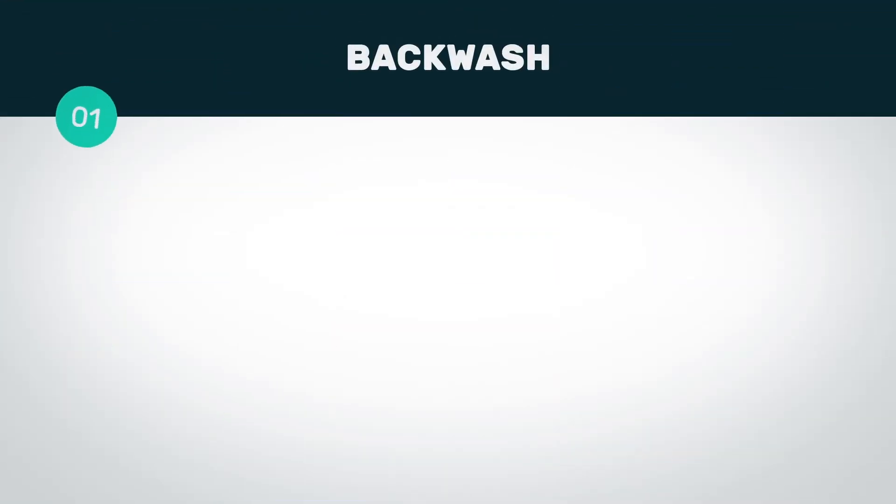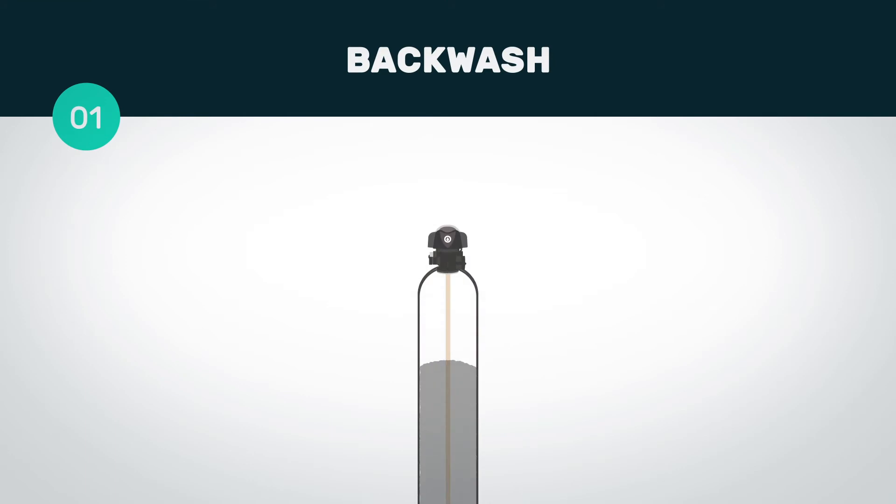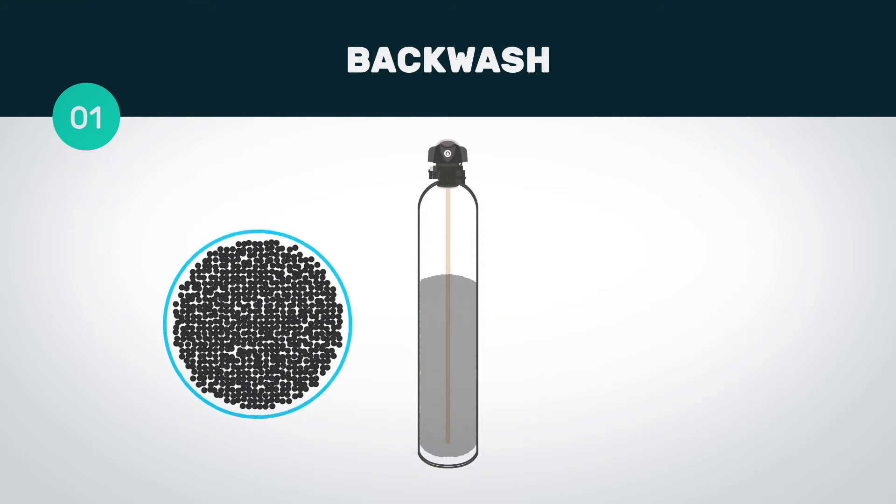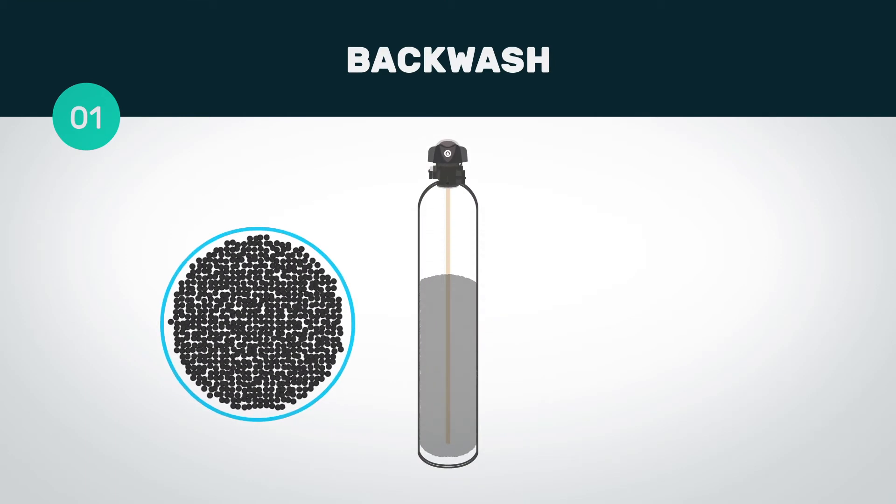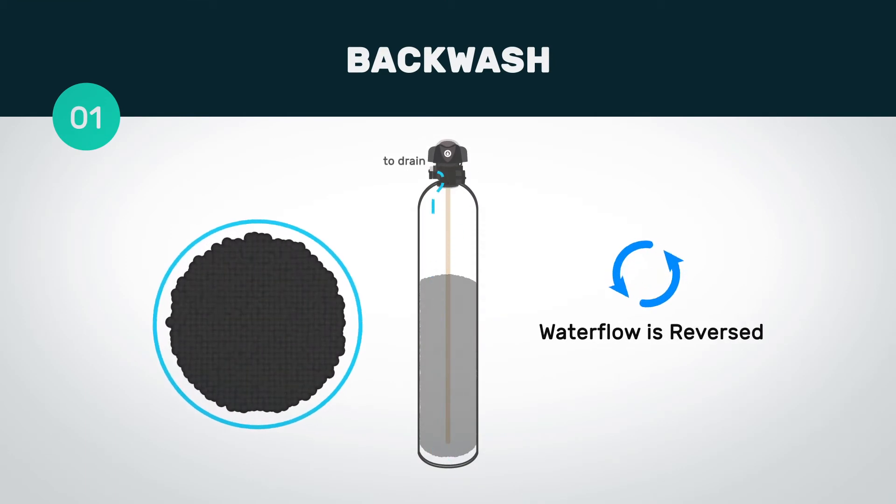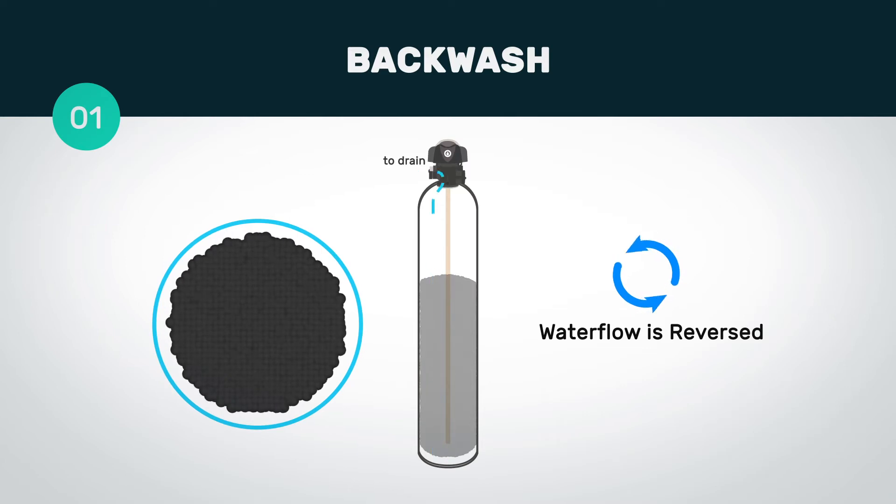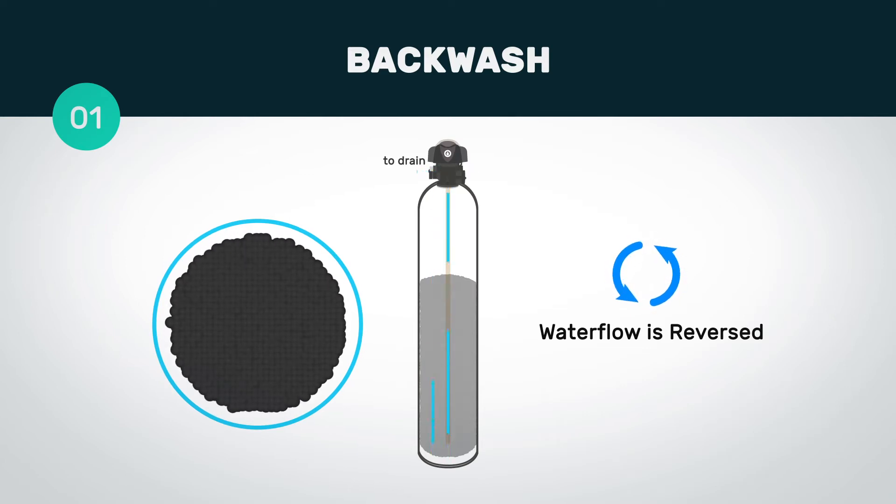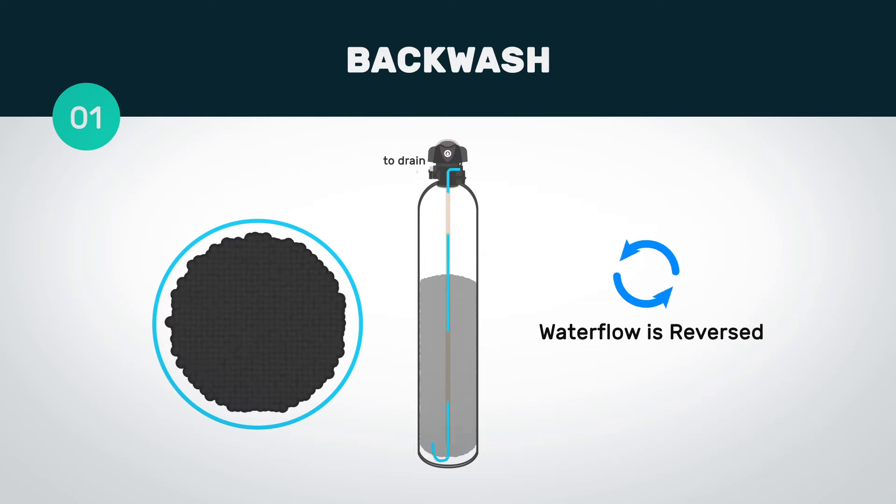During a backwash, the top control valve directs the water through the inlet and down the riser. When water reaches the bottom of the tank, it then makes its way up through the media. Through this process, the force of water lifts the media bed, creating a swirling and tossing motion.